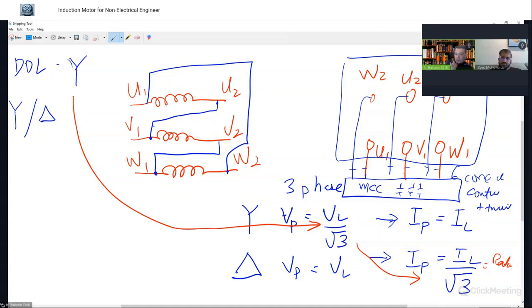But star delta, like I said just now, instead of having 3 wires that go into the motors, now we have to bring out 6 wires that go into the star delta controller. The next one is, if star delta is not viable, then we need to go for a soft starter. A soft starter is expensive. Then on the higher side will be VFD. If you go for VFD, it's more expensive. So it is actually the choice of power system engineers to make sure that when you start these motors with huge starting current, it will not affect the other items online.